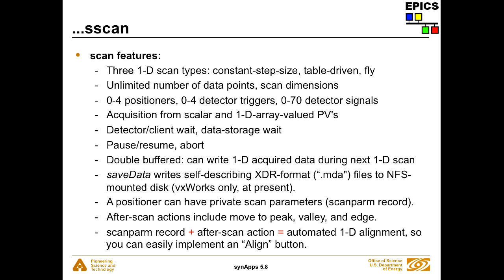There's no real limit to the number of data points or scan dimensions. You can have zero to four positioners, zero to four triggers, and zero to 70 detector signals. You can acquire from scalar or array-valued PVs. It's double-buffered, so you can acquire a new scan while the previous scan is still being written to disk. An underused feature: after a scan you can tell the scan record to look at the data in one particular detector and find a peak, edge, or feature, and automatically send the positioners to that position — enabling automatic alignment.